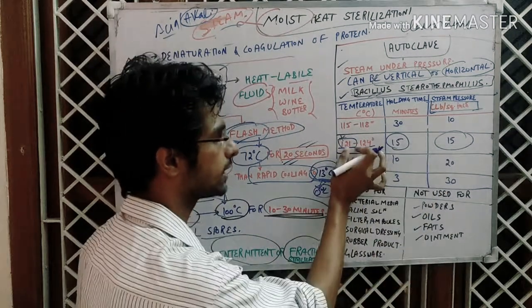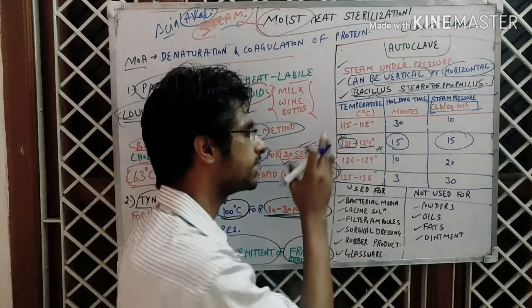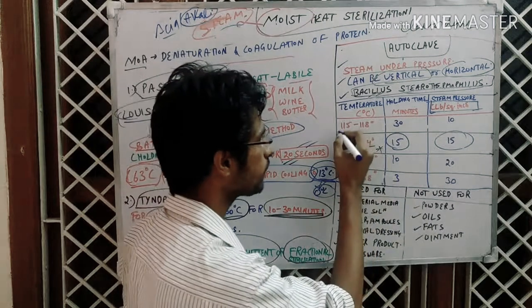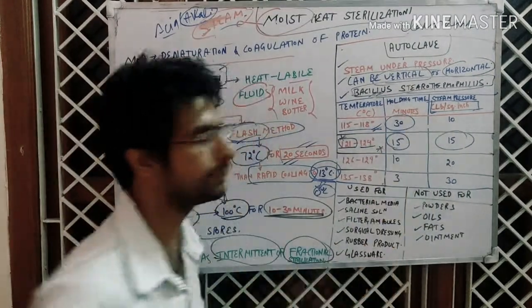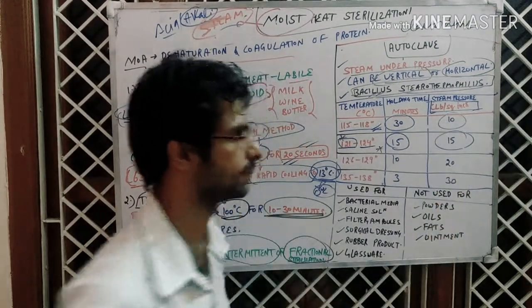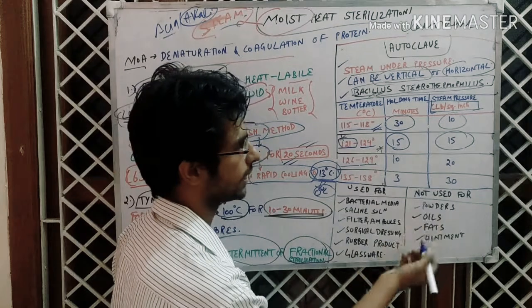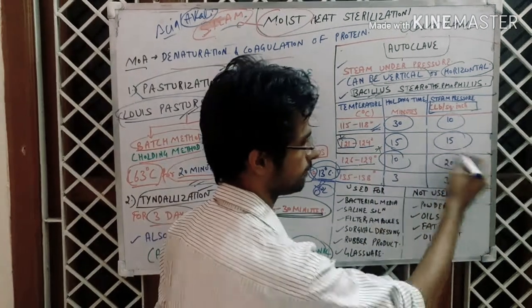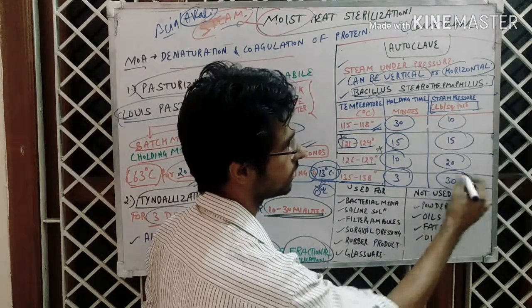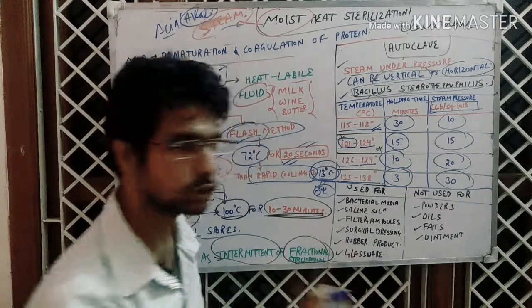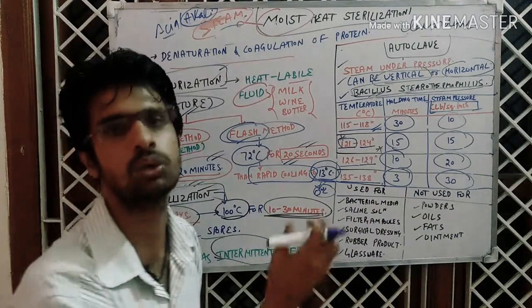This is most commonly asked in examinations, written in options as: temperature, holding time, and steam pressure. If we decrease the temperature, the time increases. At 115 to 118 degrees Celsius, the time doubles to 30 minutes and pressure decreases to 10 lb per square inch. At 126 to 129 degrees Celsius, time decreases to 10 minutes and pressure increases to 20 lb per square inch. At 135 to 138 degrees Celsius, it is just 3 minutes at 30 lb per square inch.